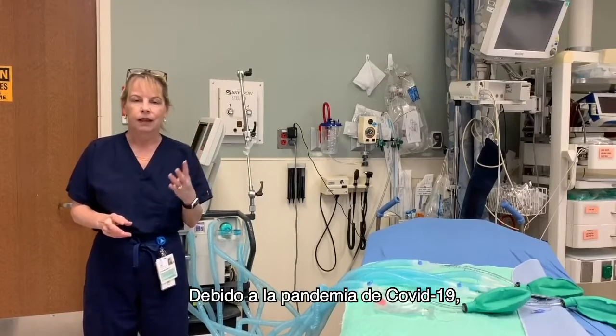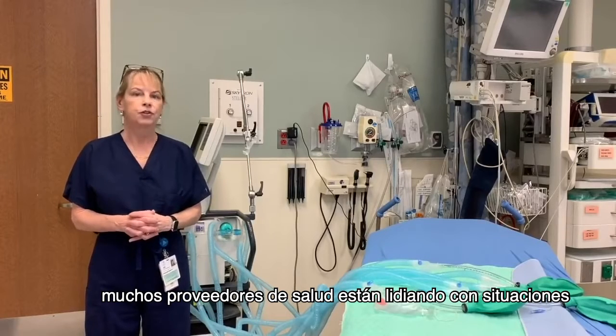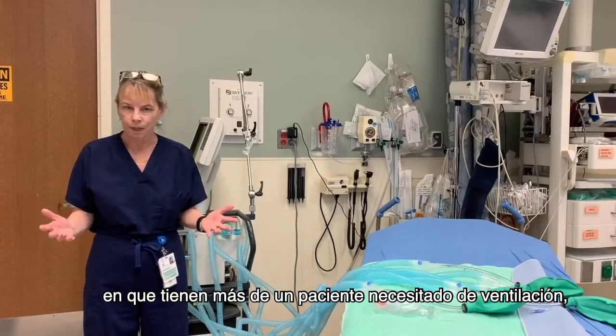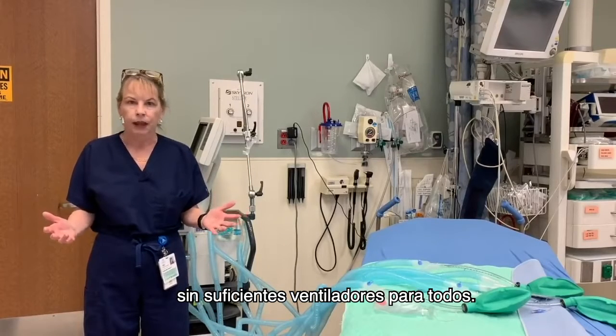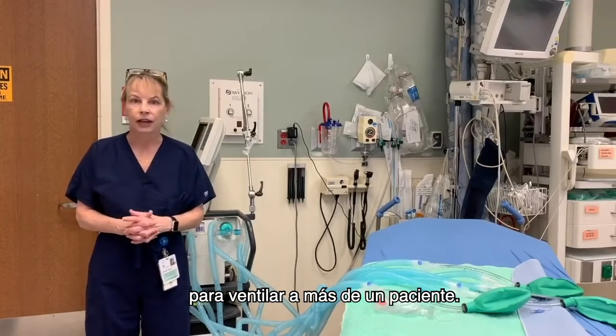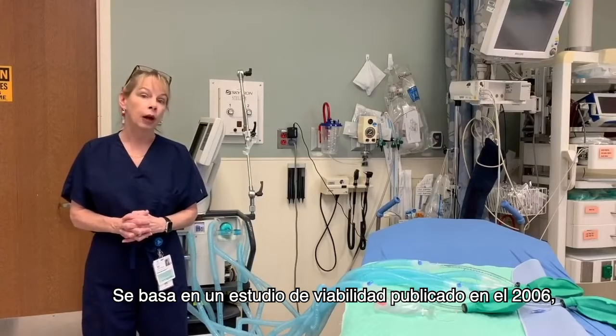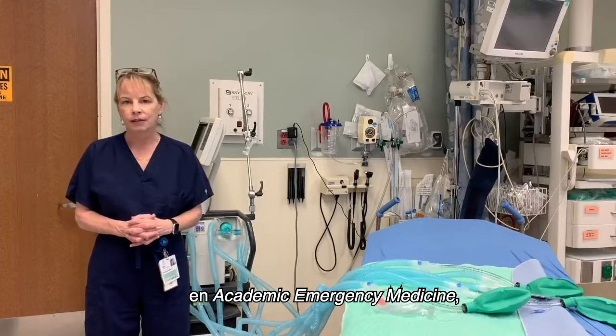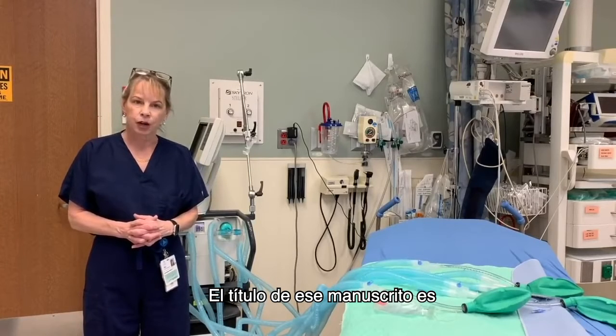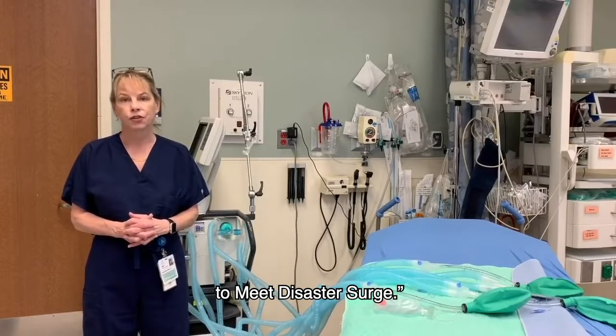Because of the COVID-19 pandemic, many healthcare providers are struggling with a situation where they may have more than one patient needing ventilation and not enough ventilators to go around. So that's why I'm putting this YouTube together, so I can show you how to modify one ventilator to ventilate more than one patient. It's based on a feasibility study that was published in 2006 in Academic Emergency Medicine with one of my colleagues, Dr. Greg Namus. The name of that manuscript is A Single Ventilator for Multiple Simulated Patients to Meet Disaster Surge.